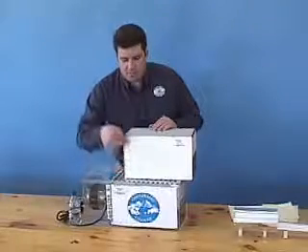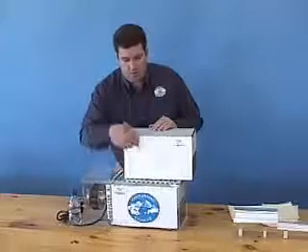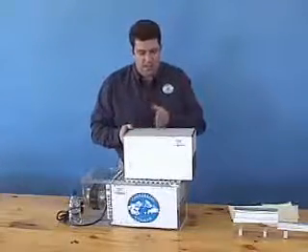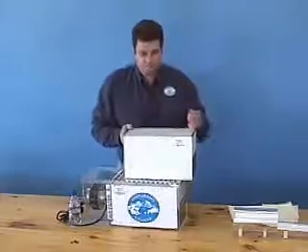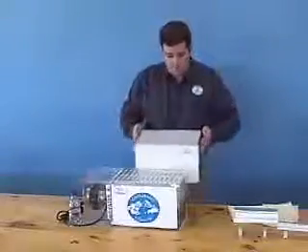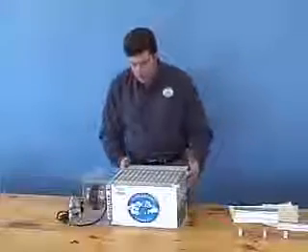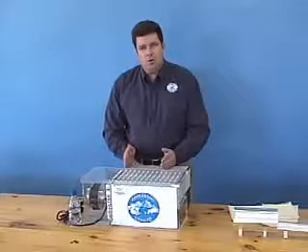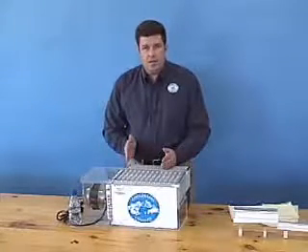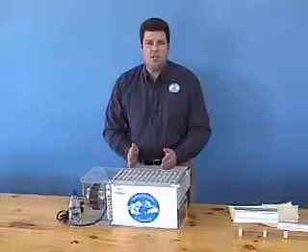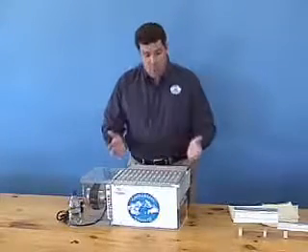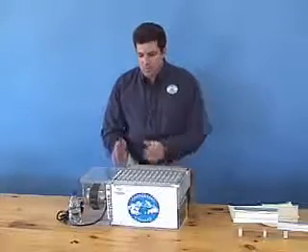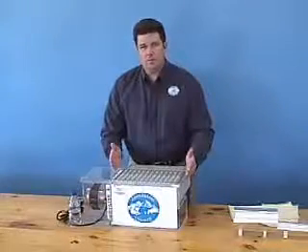This same process occurs another 12 times, incrementally cooling both the product and working airstreams as the air travels down the heat and mass exchanger. This is the heart of the Maisotsenko cycle, incrementally cooling both the product and working airstreams through heat exchange while incrementally fractioning off some air to aid in lower temperature vaporization and mass transfer. In short, this elegantly ingenious and simple process is how we achieve temperature drops that have never been seen before.